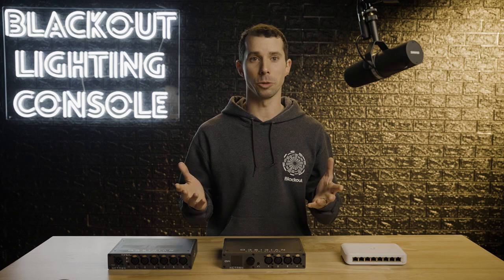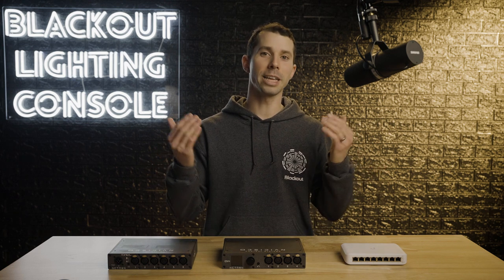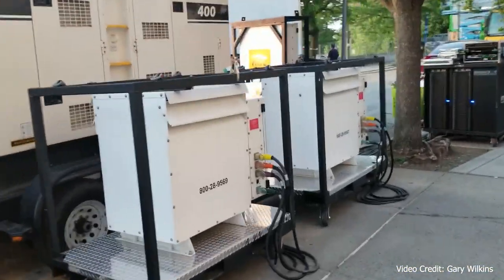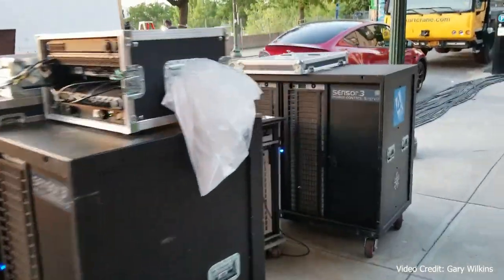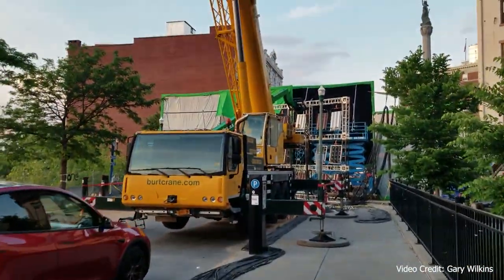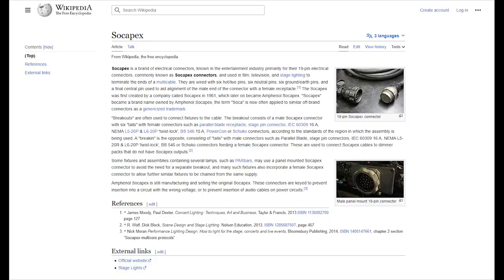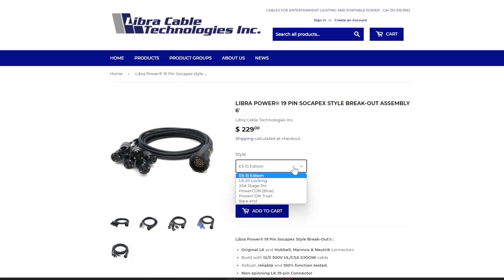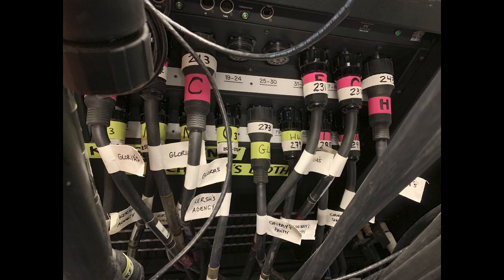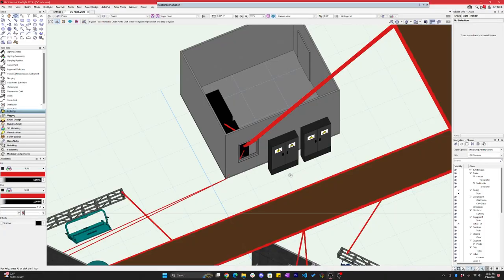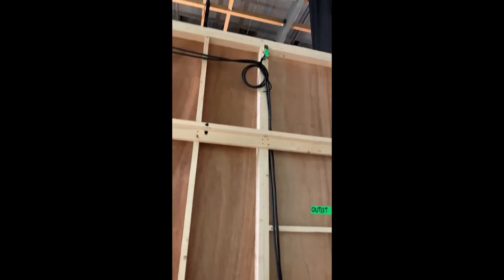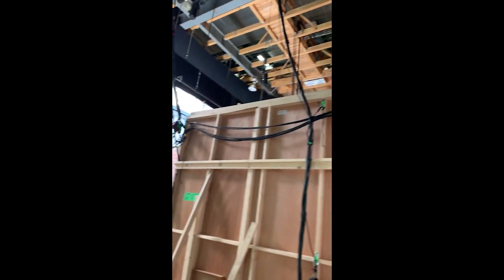Now there are two ways to do power. The first way — the old school method — is you'd run the heavy cable, your 2-aught and 4-aught, from the studio mains or your generator to your dimmer room where they would power your dimmer racks. These had to be outside the stage or in another room because they were so noisy. You then run Socapex, which is a big cable containing six individual dimmer circuits from the dimmer racks to every corner of your set. But because we have LEDs that don't plug into dim circuits, now you have to run additional Socapex that is hard power or switchable power — not dim lines. So you're essentially running two types of Socapex to key areas around the set.